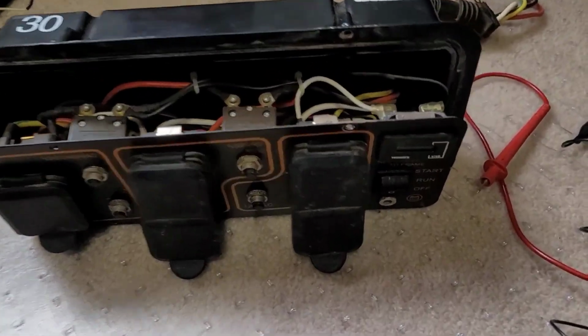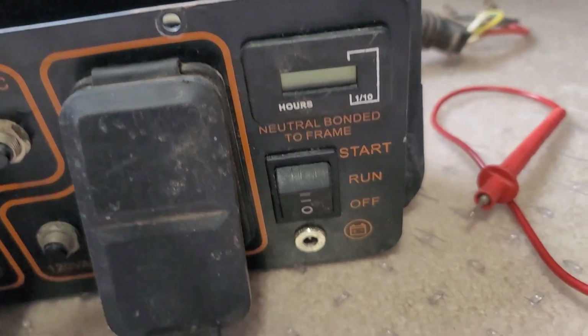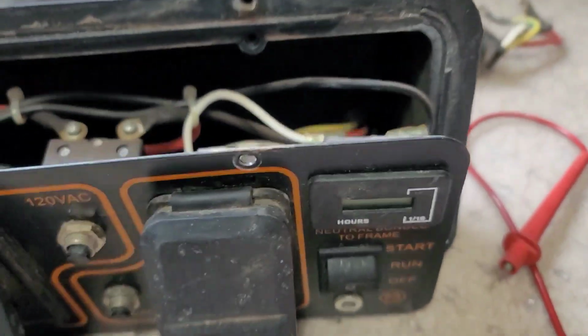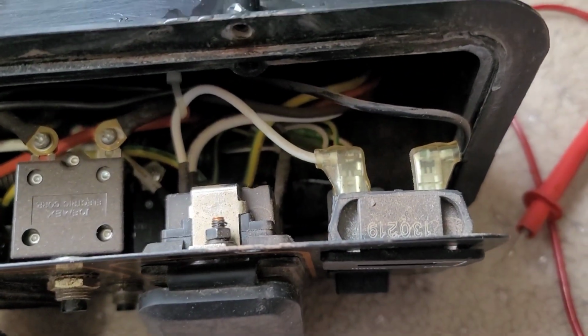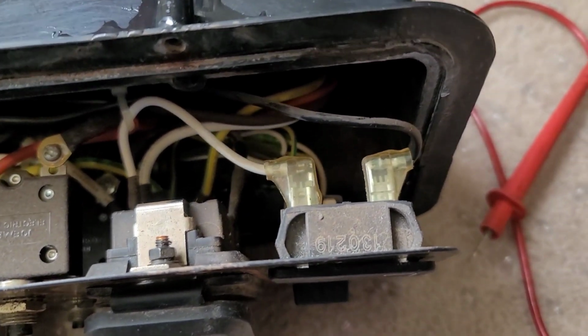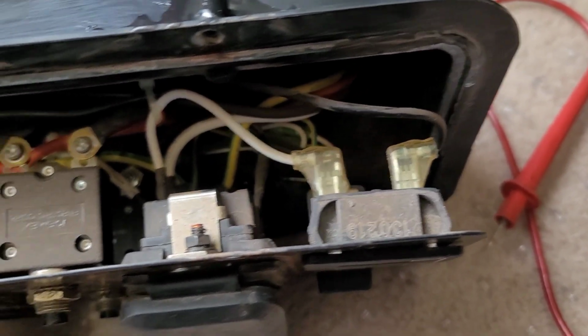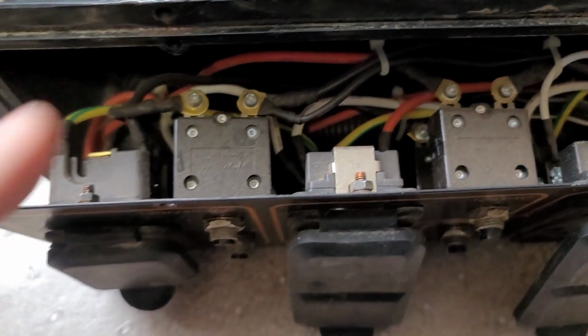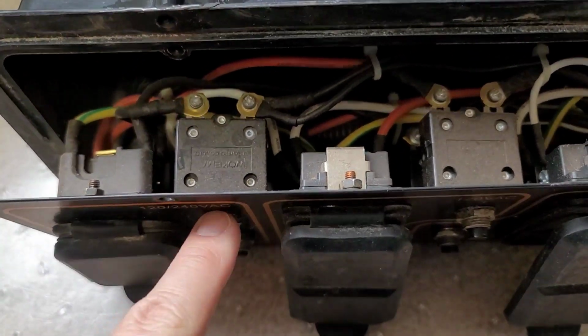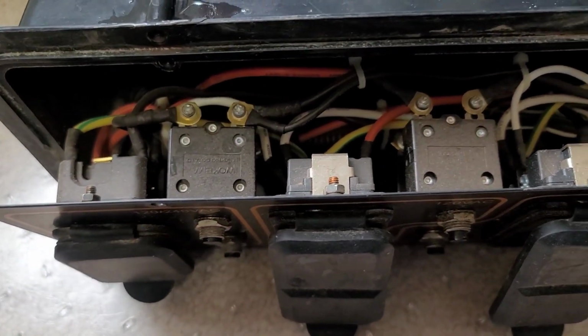The last piece I wanted to check was the hour meter. The hour meter is right here, and it is powered by 120 volts. You can see the white wire for the neutral and the X hot on the black wire, which is jumpered off of the line side of this circuit breaker here for the L1430.